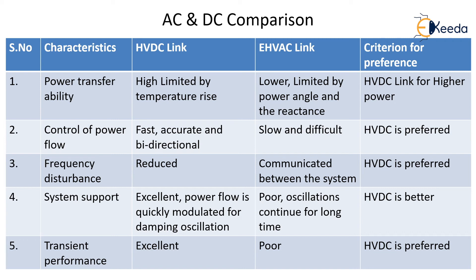Regarding frequency disturbance, HVDC reduces frequency disturbance between interconnected systems, whereas in EHVAC frequency disturbances are communicated between the two connected systems. For system support, HVDC is excellent — power flow is quickly modulated to damp oscillations. In EHVAC, system support is poor and oscillations continue for a long time, which creates stability problems. In both cases HVDC is clearly the better option.